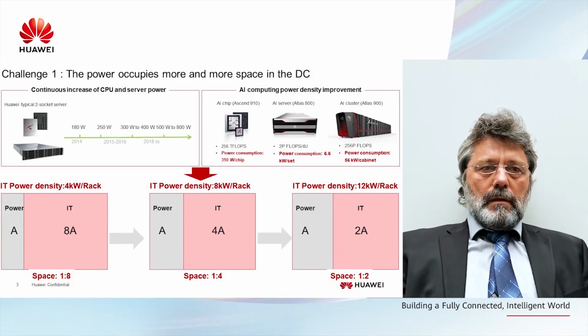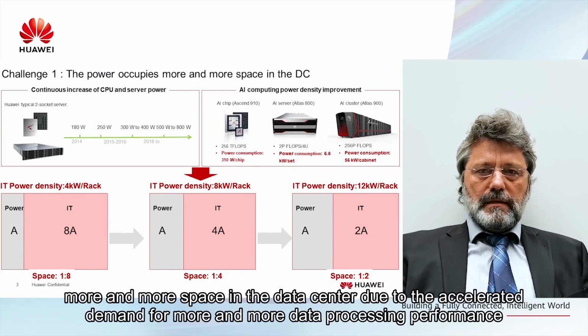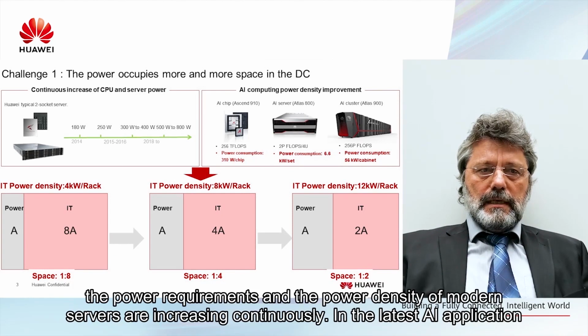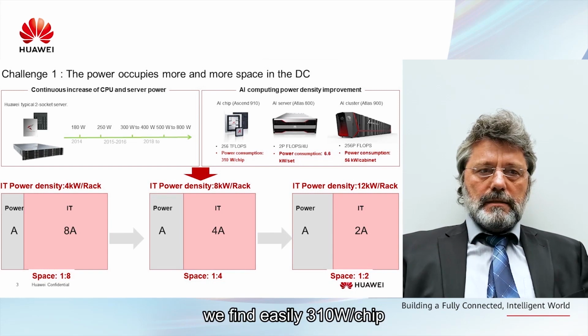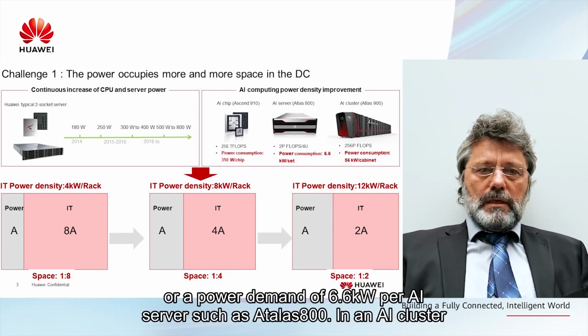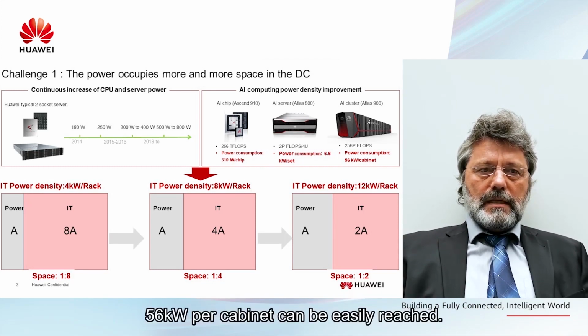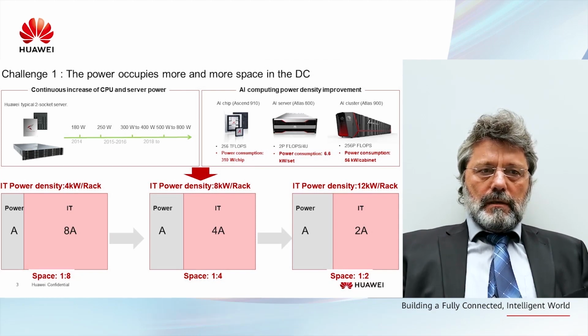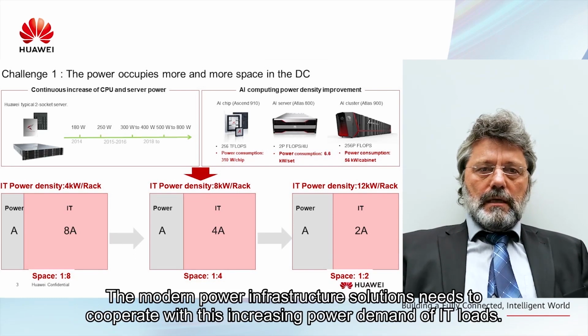Challenge 1. The power occupies more and more space in the data center. Due to the accelerated demand for more and more data processing performance, the power requirements and the power density of modern servers are increasing continuously. In the latest AI applications, we easily find 310 watts in an Ascend 910, or a power demand of 6.6 kilowatts per AI server set, such as an Atlas 800. In an AI cluster, 56 kilowatts per cabinet can easily be reached. The modern power infrastructure solutions need to cope with this increasing power demand of IT loads.